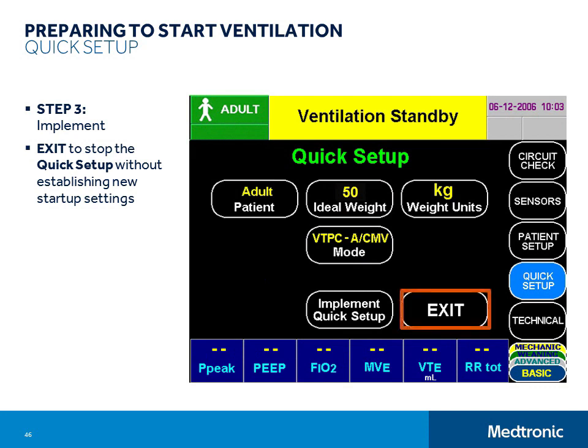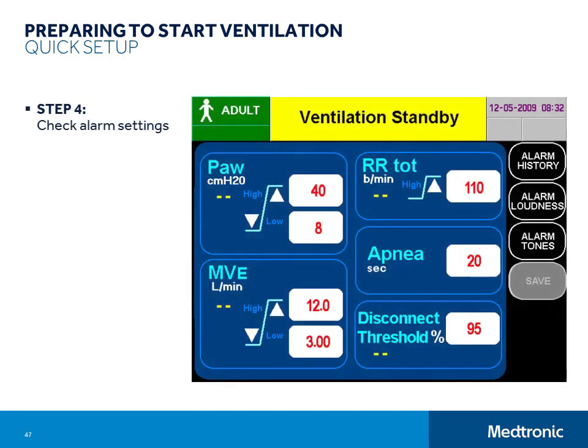To check alarm settings, just press the Alarms button on the control panel. On the alarm screen, you will find all user-set alarm limits, the button for accessing alarm history, the alarm loudness setting, and the alarm's tone selection setting. Remember that the ventilator remains in standby until Start Ventilating is touched.